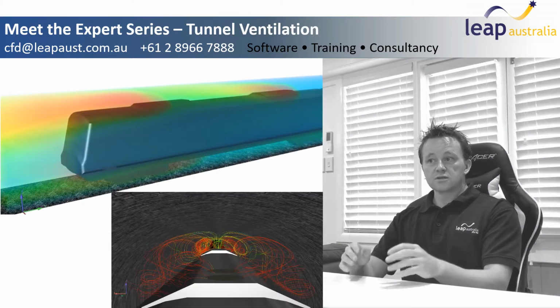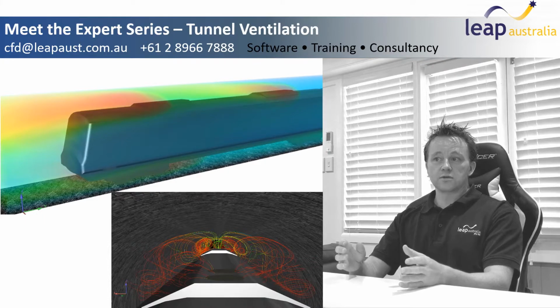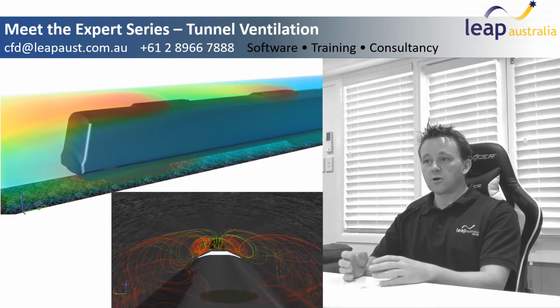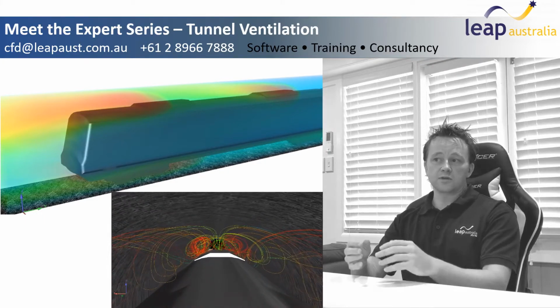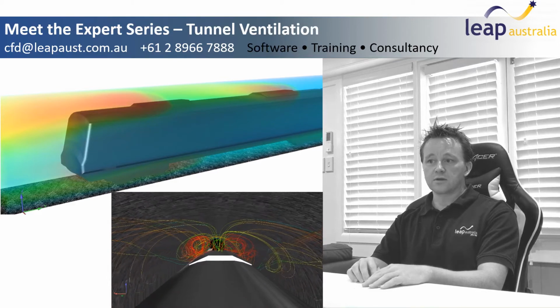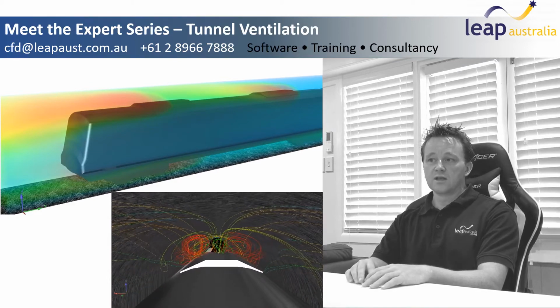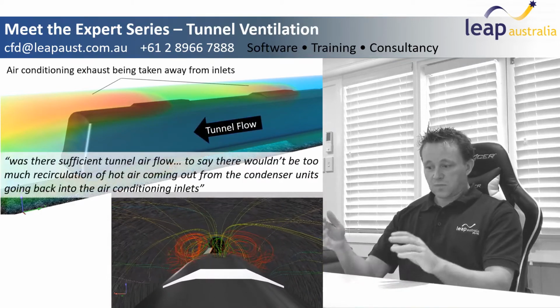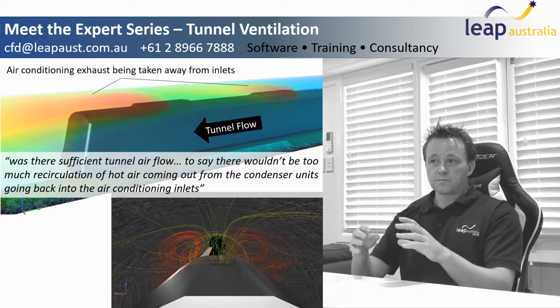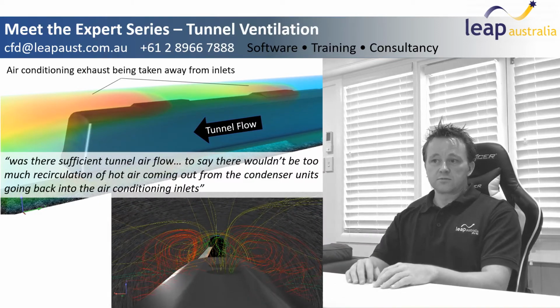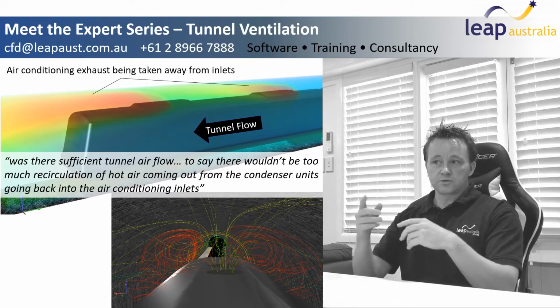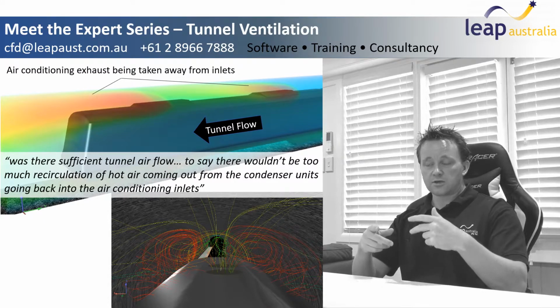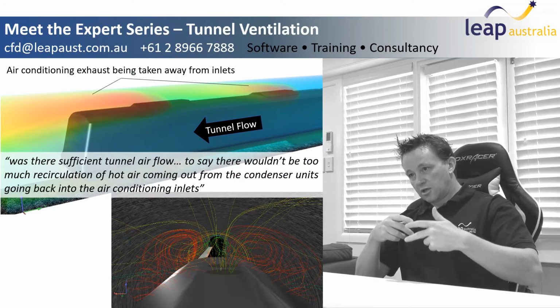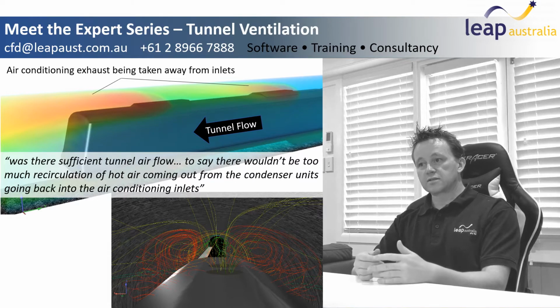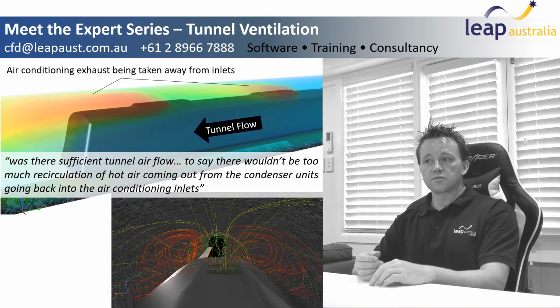When that happens, the air conditioning units are still running on the train, right? So they are still outputting hot air from the recirculation exhaust vents. And so we had to consider, was there sufficient tunnel airflow for us to say that there wouldn't be too much recirculation of hot air coming out from the condensing units, going back into the air conditioning inlets and causing problems with performance.